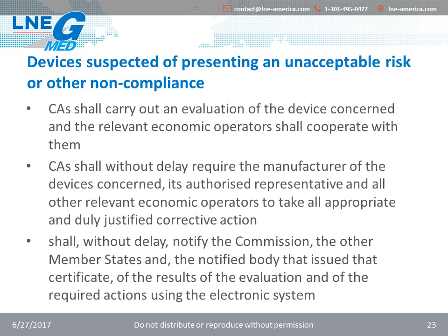Competent authorities shall first carry out an evaluation of the device concerned with the cooperation of the relevant economic operators, and then the competent authorities shall require the manufacturer of the devices concerned, its authorized representative, and relevant actors to take all appropriate corrective actions. Competent authorities also shall notify the Commission, the other member states, and the notified bodies that issued that certificate of the result of the evaluation and of the required actions using the Eudamed electronic system.